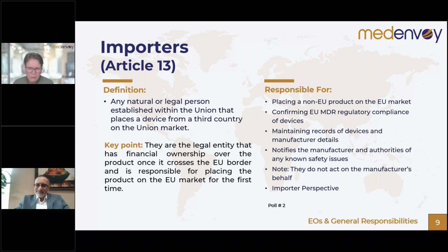Yeah, so maybe to clarify, each of the economic operators in the full supply chain of a device, from manufacturer to the end user, has their own role and responsibilities, but there is also an overlap. When we look at the role of the importer, they need to verify that the device is CE marked, that there is a declaration of conformity, whether the manufacturer is identified, and whether there is an AR identified on the labeling. They also need to identify themselves to ensure that the next economic operator in the supply chain understands that those checks have already been done.